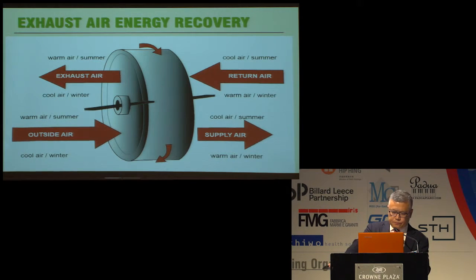Exhaust air recovery, or energy recovery, is an effective way to recoup cool energy in the exhaust air to pre-cool the outside air and reduce the cooling load. But a centralized exhaust is not always possible in hospitals because rooms requiring exhaust are numerous and spread all over the building. Also, not all exhausts are suitable for recovery, because those from the labs and fume hoods have to be discharged directly to outside. So care should also be taken to prevent cross-contamination of dirty exhaust air to the clean air side. This can be eliminated by a purge cycle and by ensuring the intake pressure is always higher than the exhaust pressure.